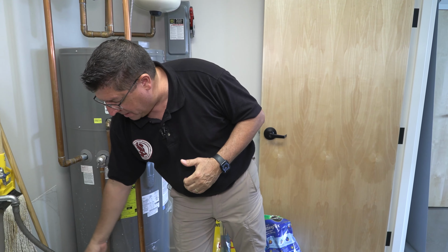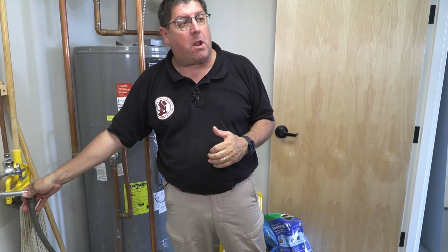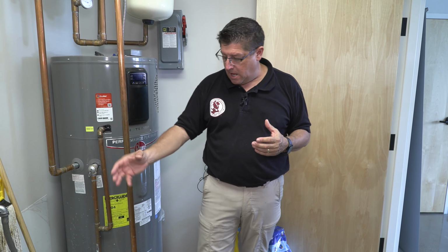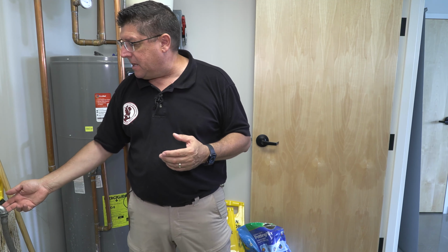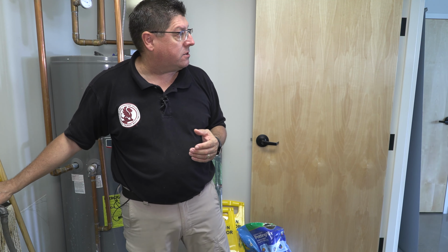But one of the issues we do have is an opportunity for cross-contamination. The cross-contamination would happen because we've installed this little bit of hose whip that is down inside the flood rim of this basin. Because it's inside the flood rim of that basin, if I was to fill that basin and clog the drain, water will slurp back up into this and contaminate the water system of the building.